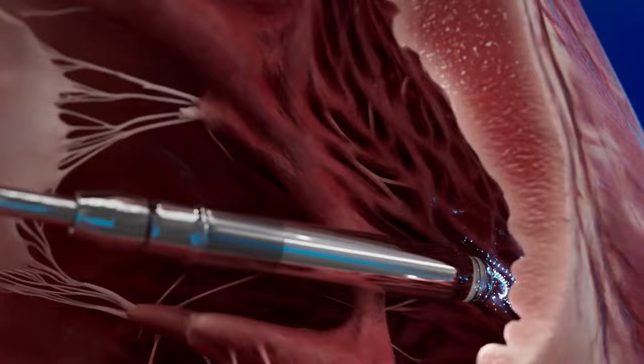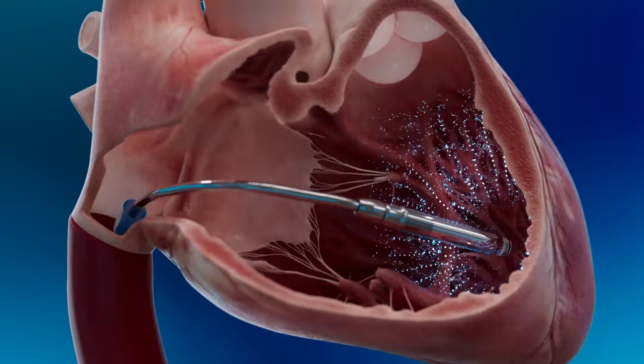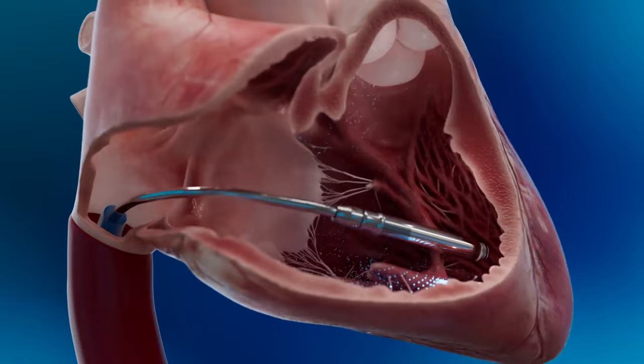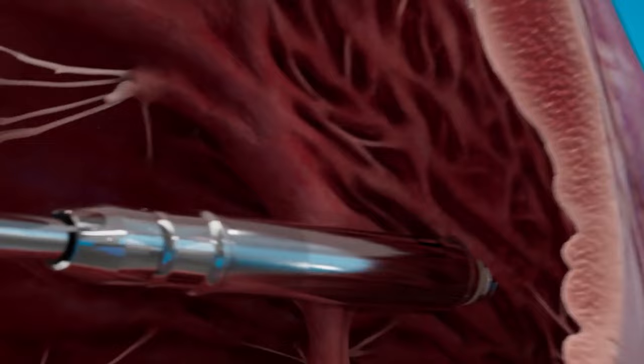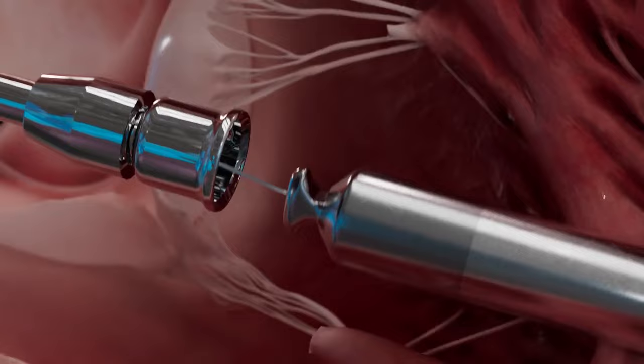While mapping, the device can measure R-waves, impedance and an initial capture threshold before fixation by simply touching the leadless pacemaker's tip electrode to the endocardial tissue — all to find the ideal pacemaker location. The device is then turned, engaging the helix into the soft tissue. The catheter is placed into tether mode to allow for final testing, and when testing is satisfactory, the device is released.